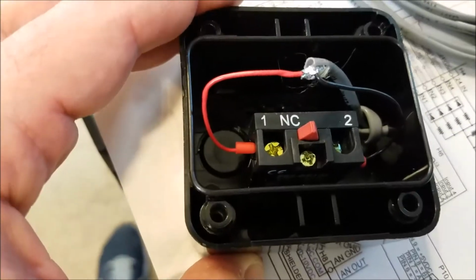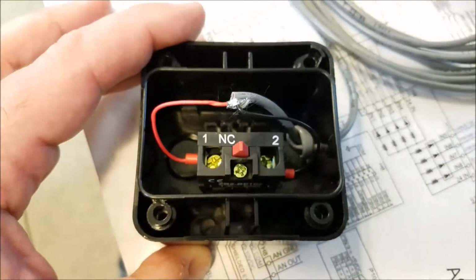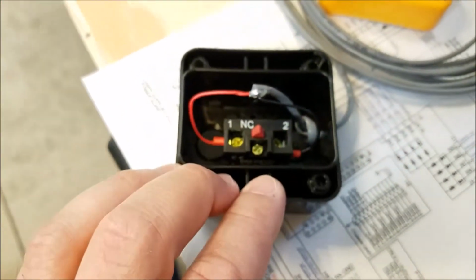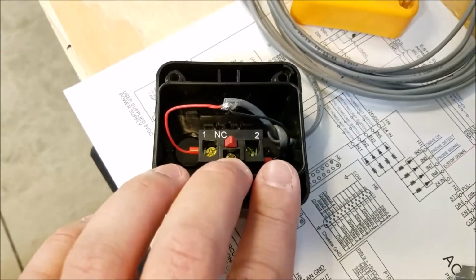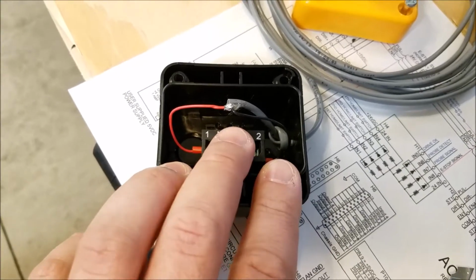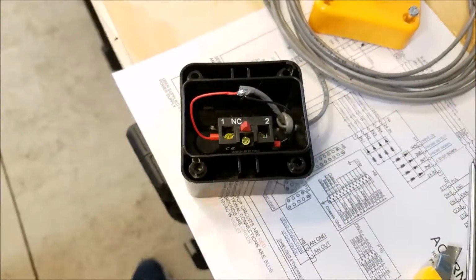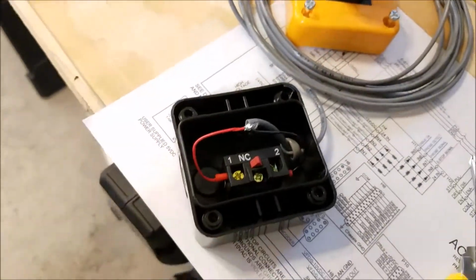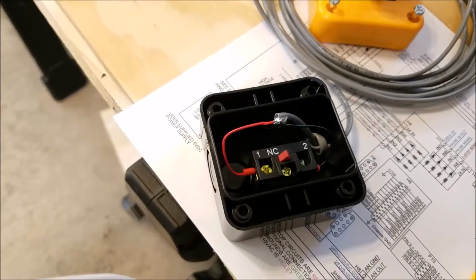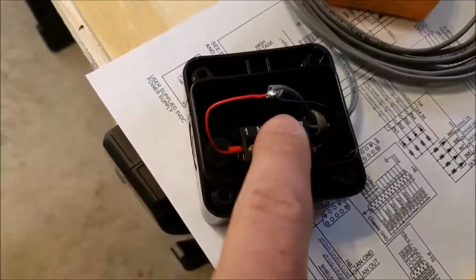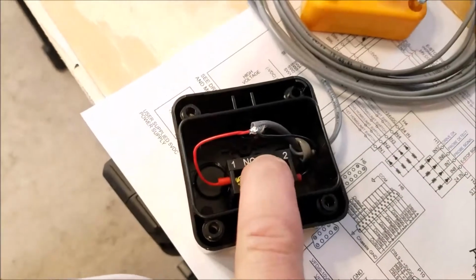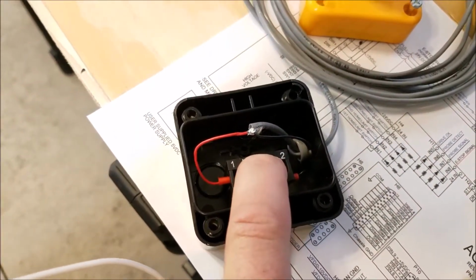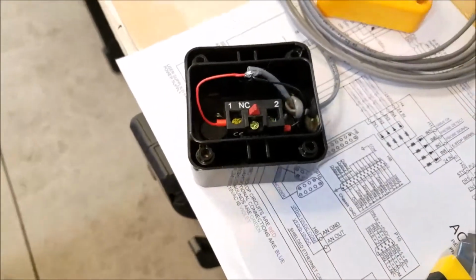Also, notice this is a normally closed switch. And that's for safety reasons. So normally closed is safer than normally open, in my opinion. And I'll tell you why. Normally closed means everything is system normal when the circuit is closed. If the e-stop is pushed and the switch is pushed down, it breaks the circuit. It opens the circuit and it triggers the alarm. So normally closed is good.